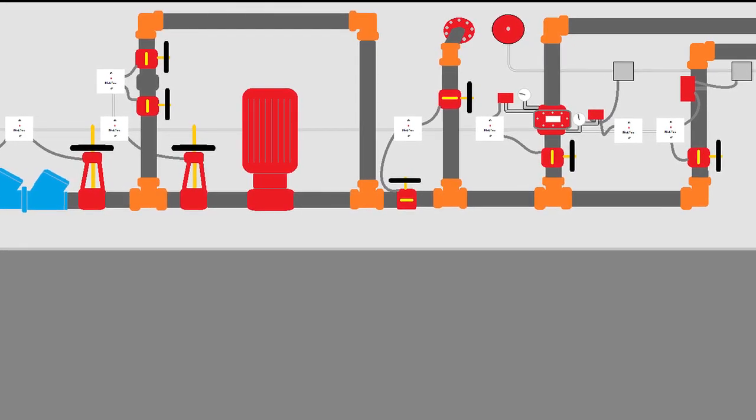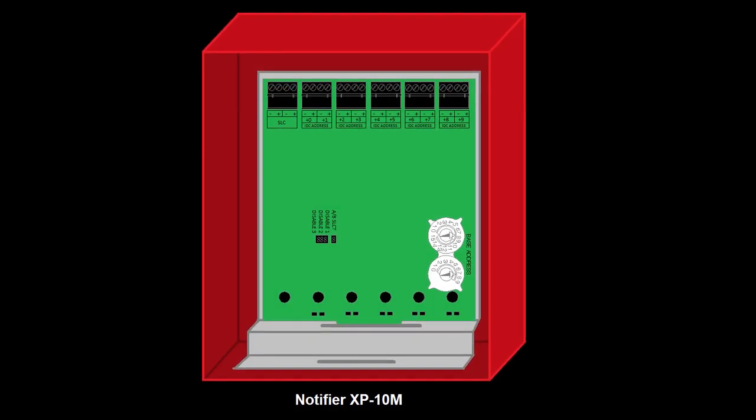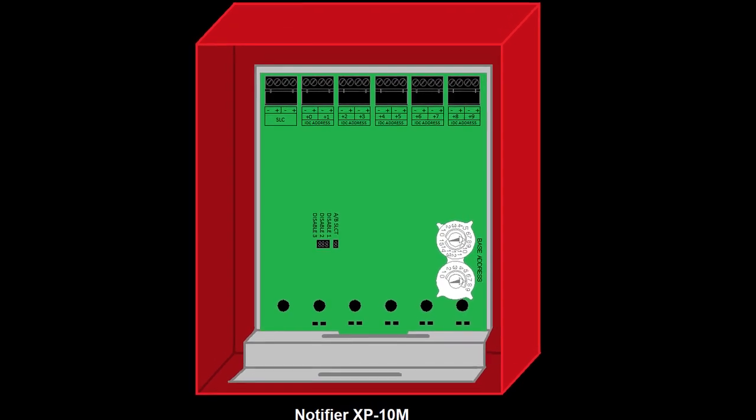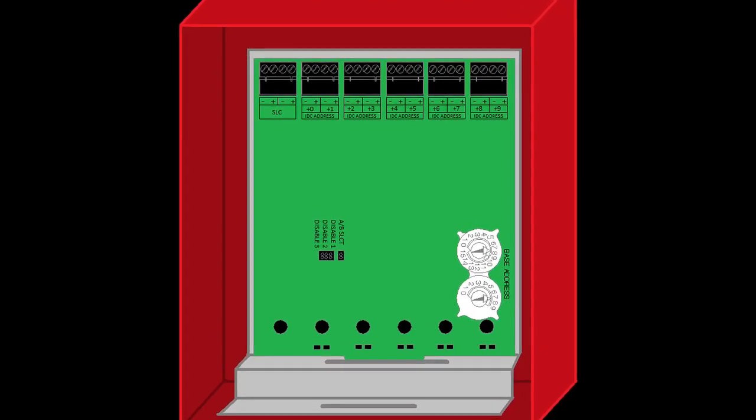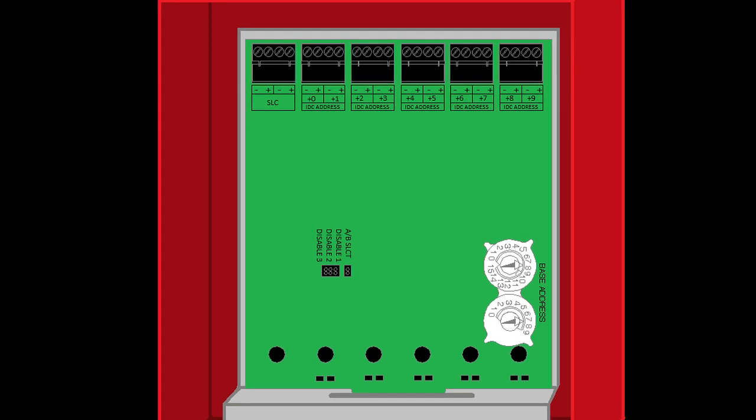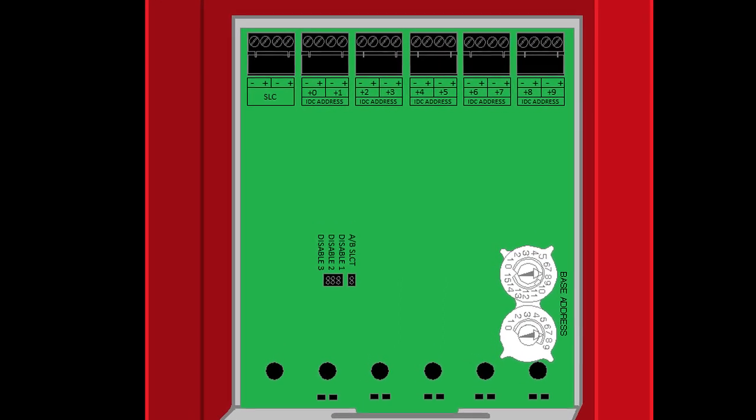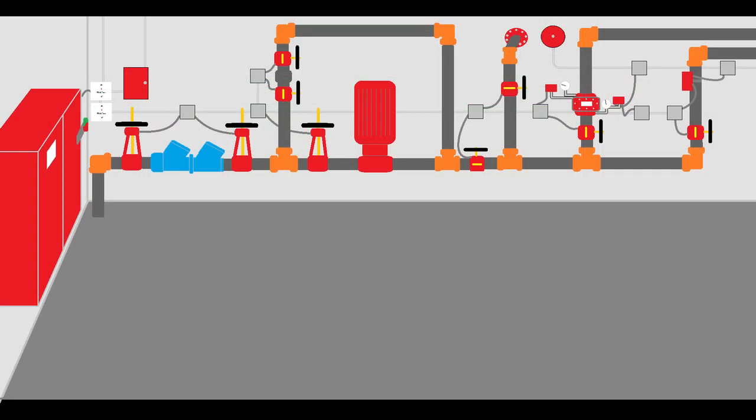Another option is to utilize a 10 point monitor module that Notifier makes for our first 10 points, then a single and dual monitor module for the remaining devices. If I were designing this room I'd probably prefer the individual modules by each device. I think it makes it a little bit easier for troubleshooting purposes because you can easily see which modules are monitoring which devices. But because I want to show how the XP10M gets wired, we're going to use that in this application.